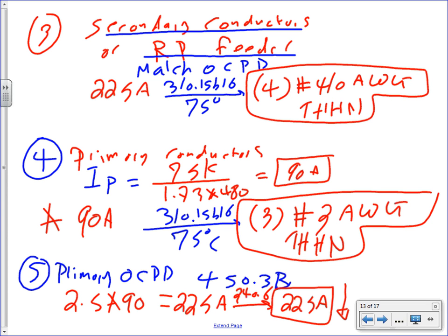Now, if you have done it before with certain transformers, like you guys at Egan, you would do it all the time, and we know that on a 75 kVA transformer, on the primary, we can put 100 amp on it or 150, and that's good protection for it based on the size of the transformer and the type and the manufacturer. Is there anything wrong with that? No, that's the max. I can't emphasize this one enough, because I don't want you to go to work and see people putting a 200 amp on it or 150 and say, what the heck is Chad talking about? That's the max.